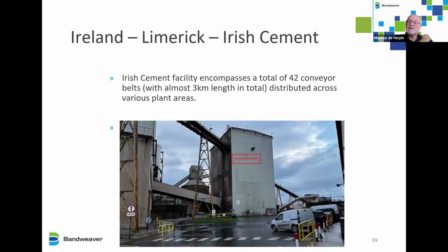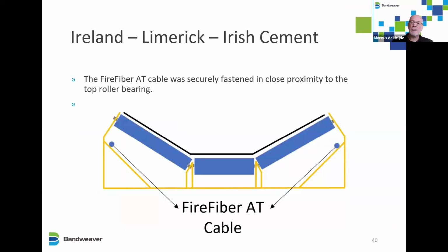So the next example we've got is an installation I went through myself in Limerick. It's the Irish cement facility. There is 42 conveyor belts there with 3 kilometers in total in length. We only did a few of the belts there to start off with, and the crew on site, they've installed a few more conveyor belts themselves afterwards, because we gave them some training in how to do that. So this was the frame setup there. So we installed the cable as close as practically possible to the bearings, close to the top roller.